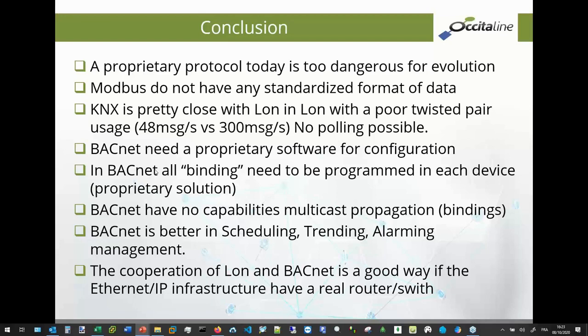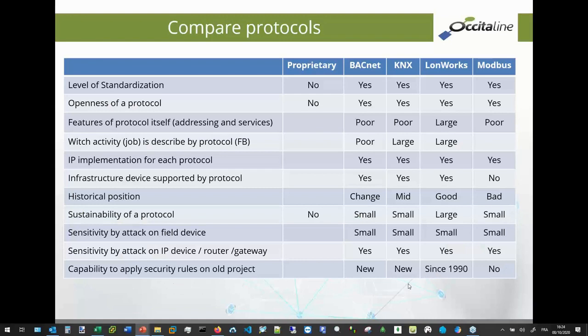BACnet, versus LON, KNX, and Modbus, is better for many things. BACnet is better in scheduling, in trending, in alarm management. BACnet is better used in the automation layer, not on the field, because you lose a lot of things there. On the field layer, it's very important that we cooperate with a second protocol such as KNX or LON. Why? Because the field needs to be protected from attack. The second reason is that BACnet does not support some connections between devices, and KNX or LON will support them. It's very important that we have something autonomous on the field.